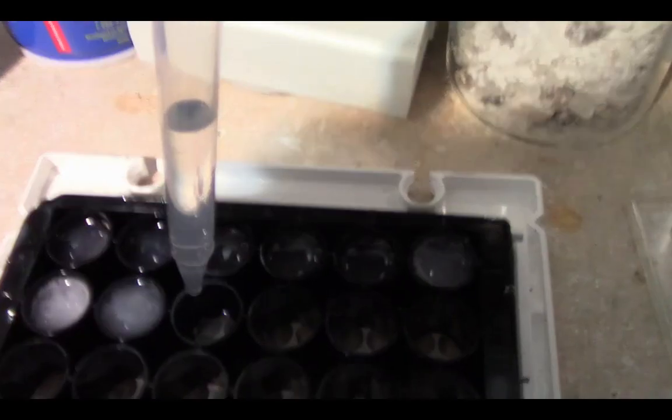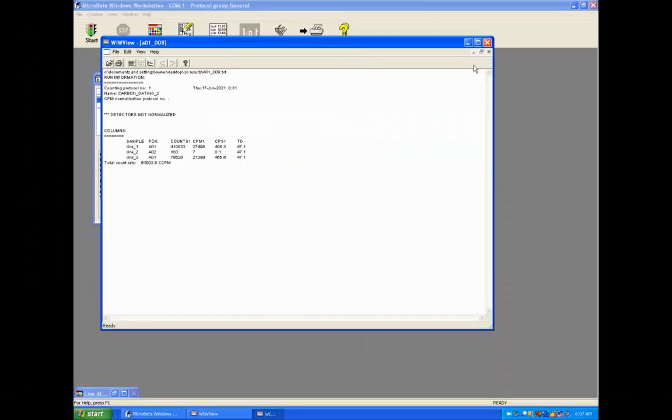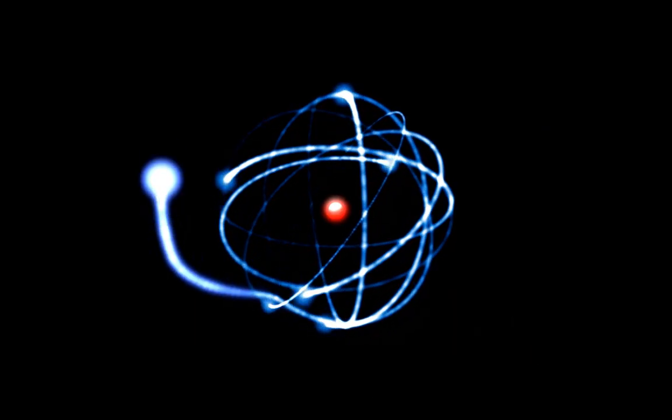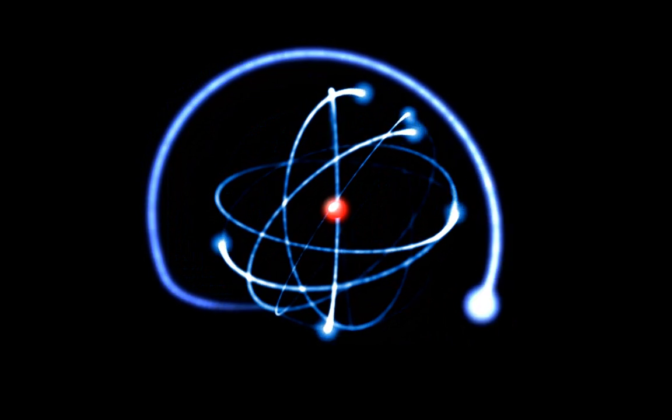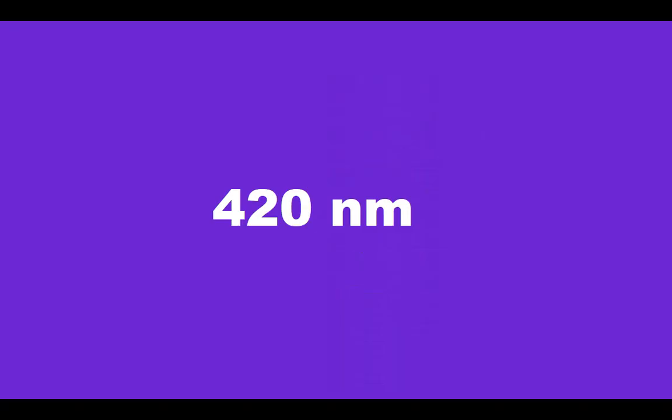On the other hand, the thorough mix of detection medium and sample allows for greater efficiency and better count resolution. This works because the beta radiation from the source has enough energy to excite the scintillation cocktail, and the excess is then re-emitted as visible photons of light around 420 nanometers.